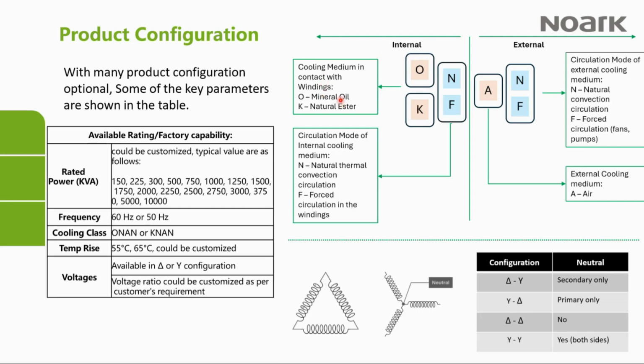So we have the internal cooling that has to do with the cooling medium, which is either mineral oil or natural ester. And on the external side, we use air for the cooling, and that's what is represented here. So when you see an ONAN transformer, what it's saying is that the transformer is using natural oil to cool the transformer, and then natural air also on the external part to cool the transformer. If you see a KNAN, it means it's a natural ester and air also. Sometimes you can have forced air or you can have forced oil.